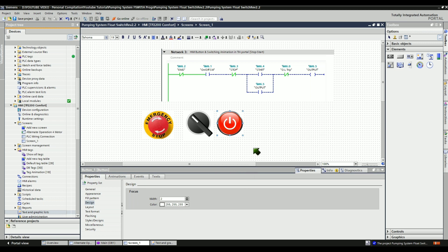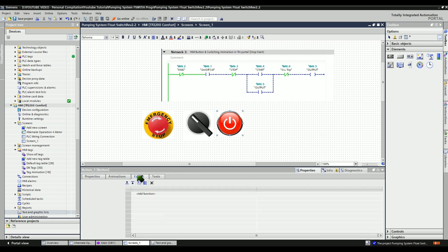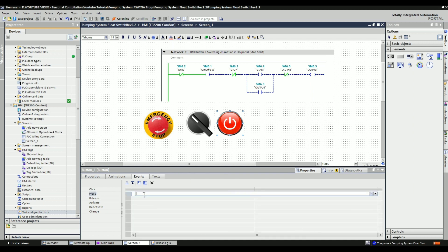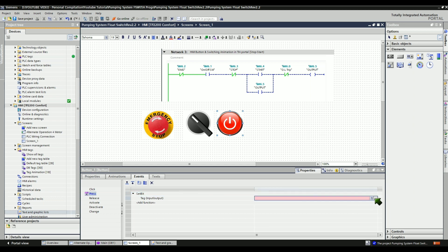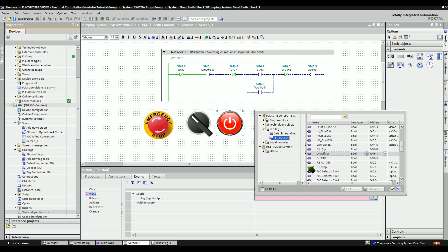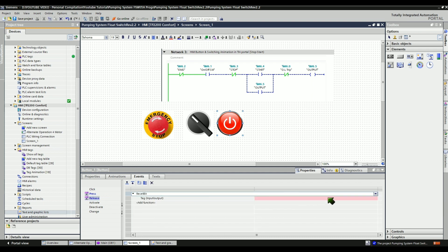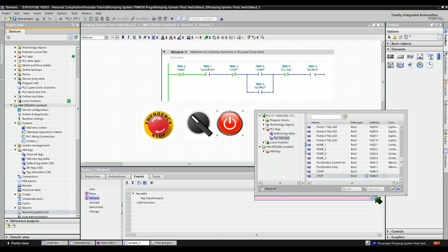The functionality must also be configured as a push button. To do this, go to the Events menu, select the Press event, and then click Add Function. Type 'SetBit' without space. The global tag of the stop push button is M6.3 memory bit. Let's configure the functionality as a stop push button when the button is pressed — this button must be connected correctly to the global tag on the CPU, otherwise it will not work properly. And when the button is released, click Add Function and type 'ResetBit' without space. Again, the global tag of this stop button is M6.3 memory bit.